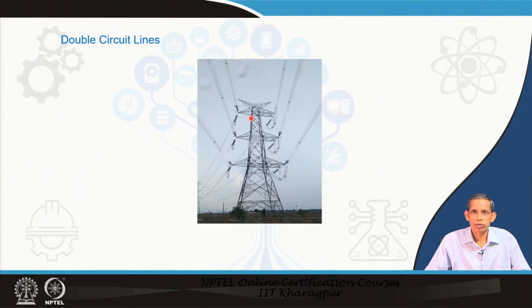Now, in such a case we see that on the same tower both circuit 1 and circuit 2 are available, and that is the issue which arises and needs special attention from a protection perspective. We will see. Now, let us consider a simple double circuit system. However, double circuit or otherwise called parallel lines can run on the same tower, can be running on different towers on the same nearby right of way. They can be terminated at different nodes. They can have a common bus also, and the other bus may not be common. So, there can be different configurations of double circuit line in a power system.